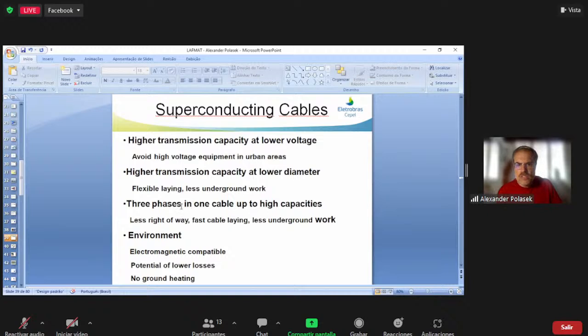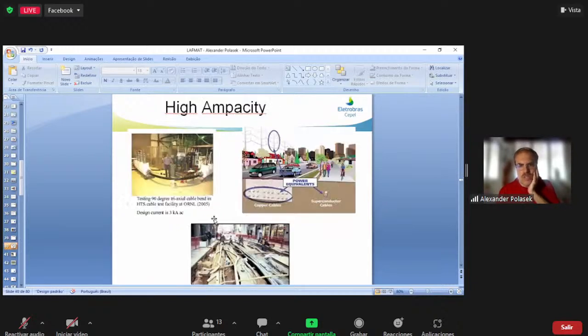It's possible to put the three phases in just one cable, depending on the geometry, on the architecture, and you have fewer environmental problems than conventional underground cables. Of course, we are talking about underground cables because they need the cooling system. You can see here a comparison between a superconductor cable, conventional underground cables, and conventional overhead line, and it's very important because you can save space, which is very critical for urban areas.